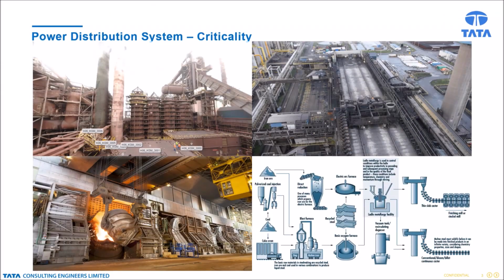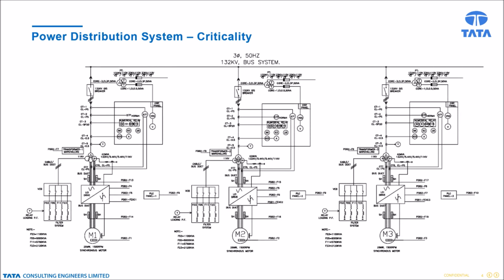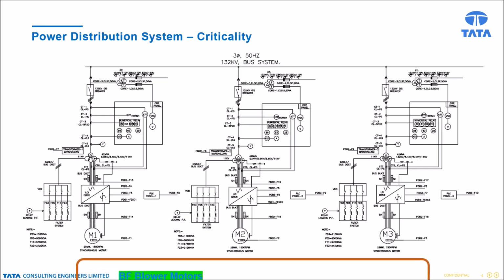Power distribution system in an integrated process plant is different from any other industrial plants due to the nature of load and its magnitude. As for example, an integrated steel plant of large scale consists of various process plants, non-process plants, services and utilities. Steel plant being a continuous process plant with high capital expenditure, design of power network should be realized from criticality point of view so that any eventuality such as grid power failure, power equipment failure and internal power system disturbances due to poor power quality can't drive the processes into jeopardy, resulting in huge capital damage associated with financial loss due to loss of production.